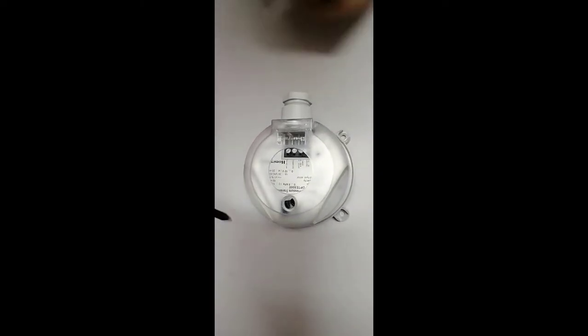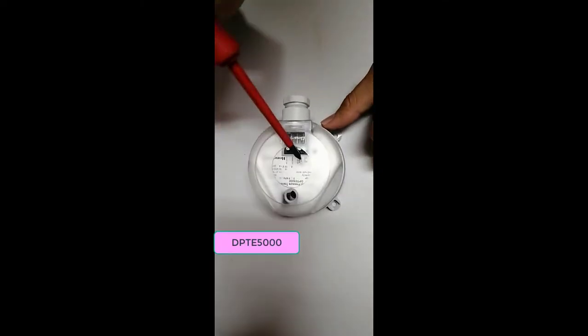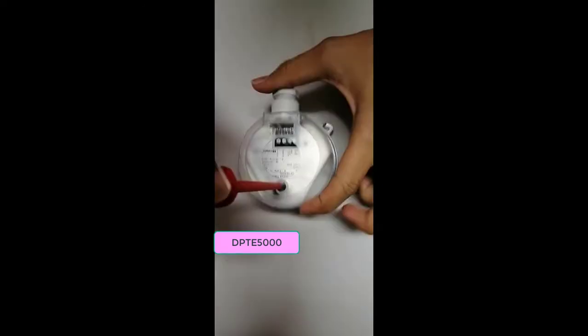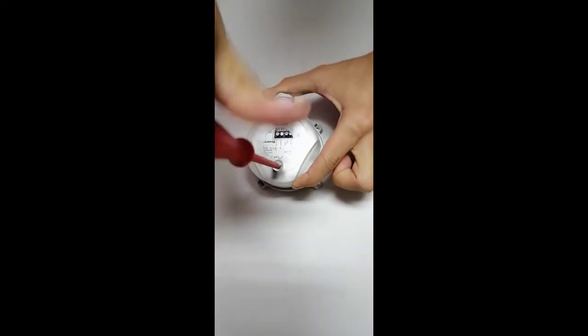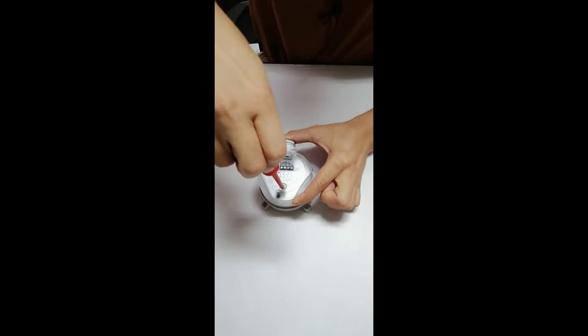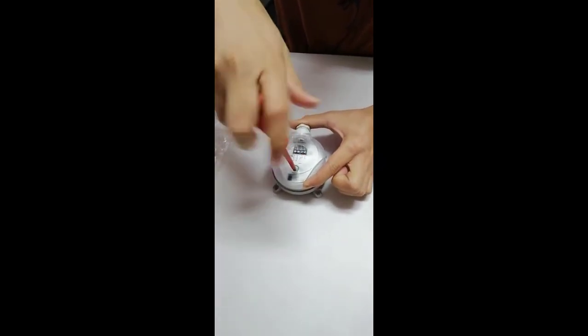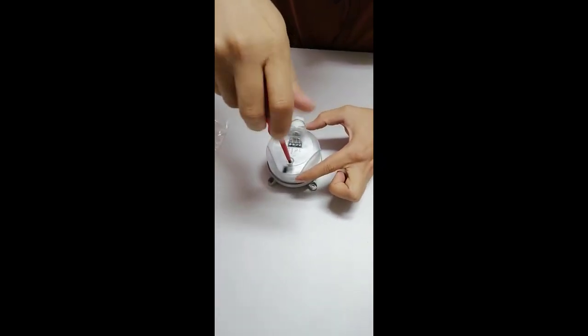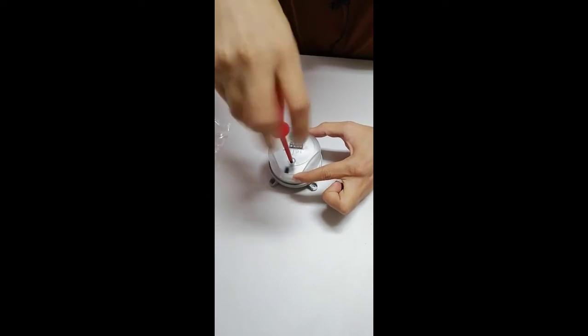This is a differential pressure transmitter. This is used to detect air differential pressure. This part number is DPTE5000 from Honeywell. Okay, so let's open this one. In shape it is similar to differential pressure switch, but its function is different. Okay, you can watch my video on input devices.